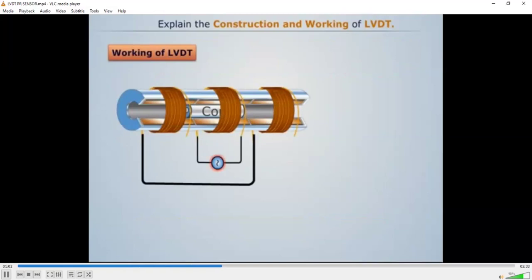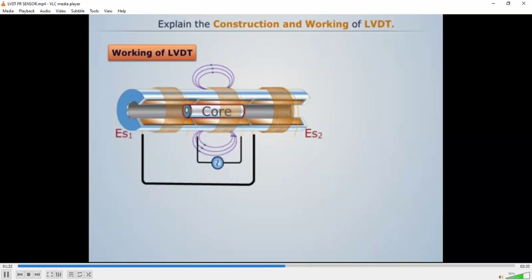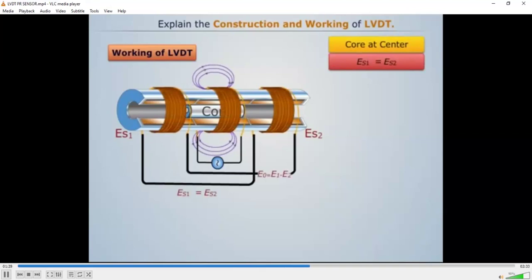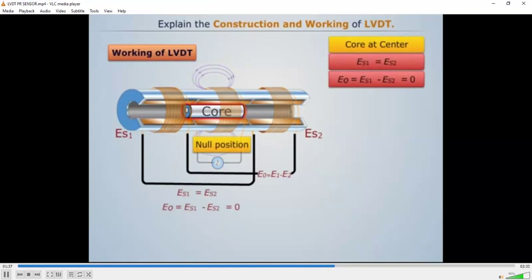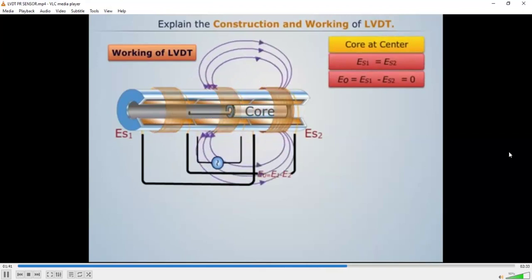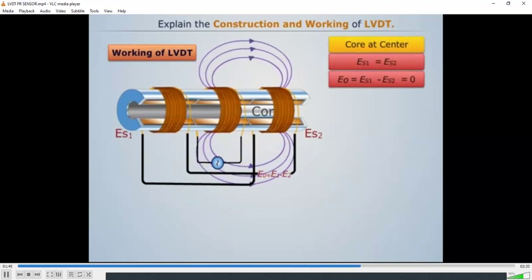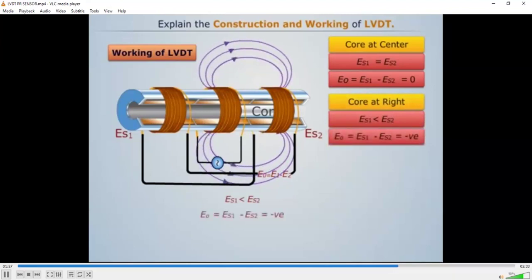When an AC source is activated, alternating current flows through the coil, producing a varying magnetic field. When this field interacts with the secondary coils, an EMF is induced in both. Initially the core is placed so that equal EMF is induced in both coils, making the net EMF zero—this position is known as the null position. Now, if we move the core towards the right, the flux linking with coil S2 becomes greater than the flux linking with coil S1. As a result, the EMF induced in S2 becomes greater than in S1, and the net EMF shows a negative value.